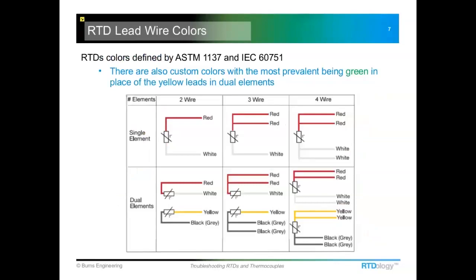Outside the probe, these lead wires have a specific color code that helps identify a couple of things: most obviously whether it's a 2-, 3-, or 4-wire circuit. The color codes can also help identify the temperature coefficient, defined by either the ASTM or IEC standards for RTDs. They define a temperature coefficient of 0.00385. If you have a sensor with two red leads and one white, that's a good indication it is a 0.00385 temperature coefficient sensor.